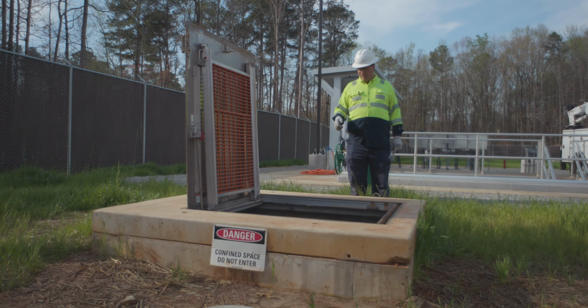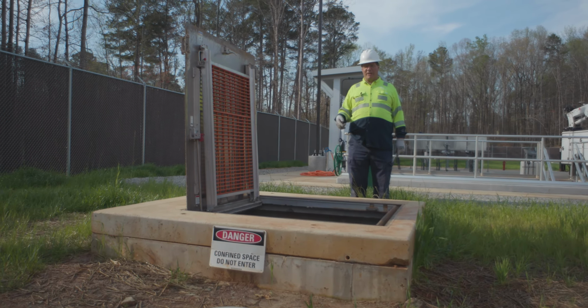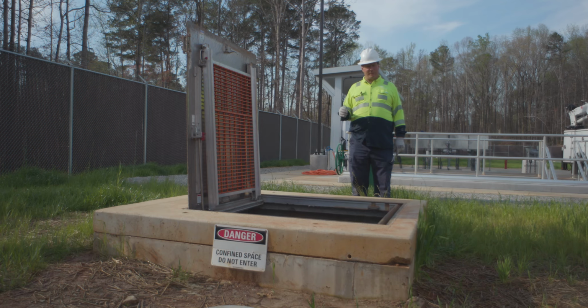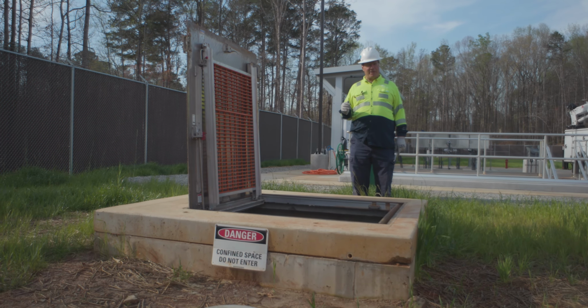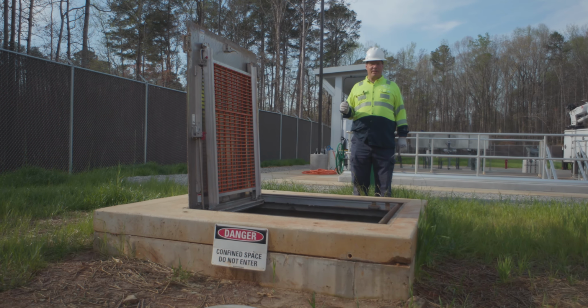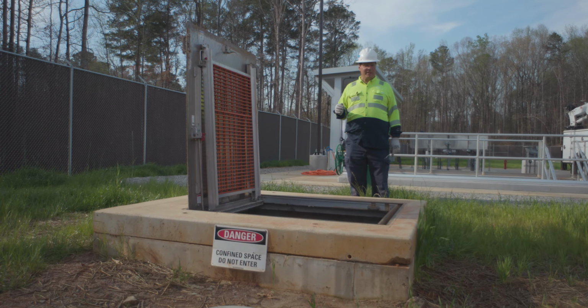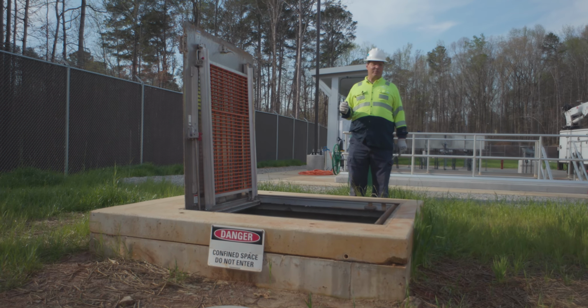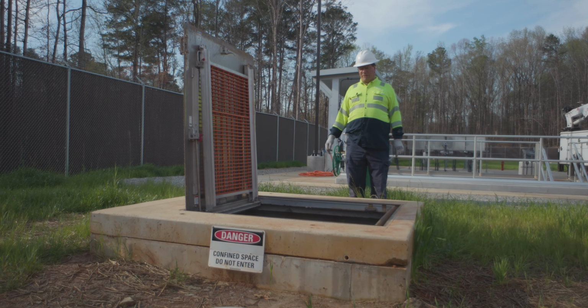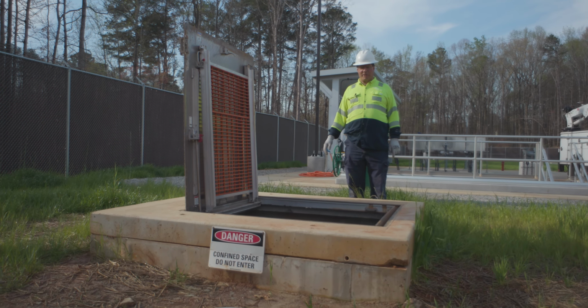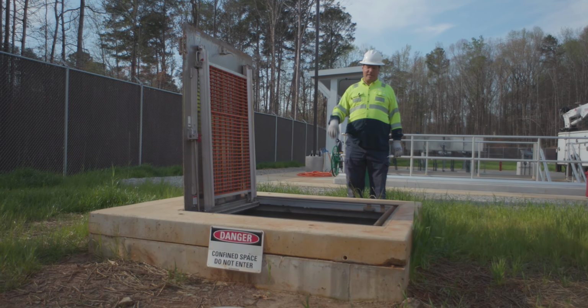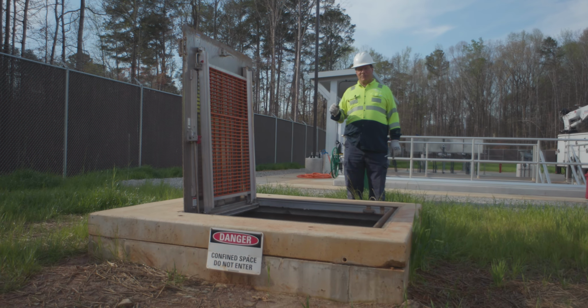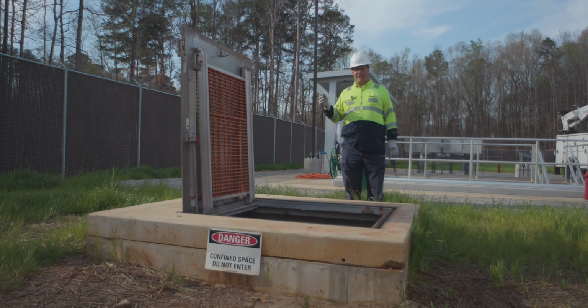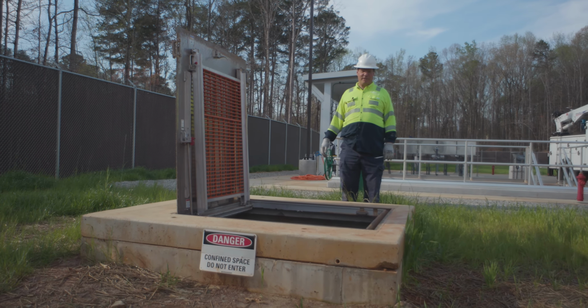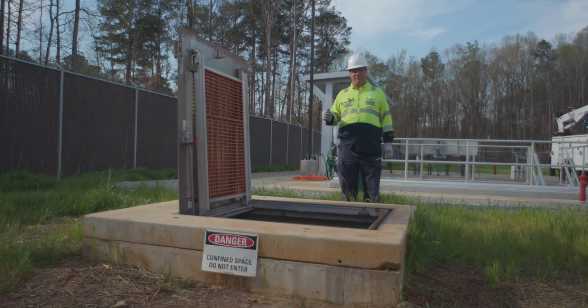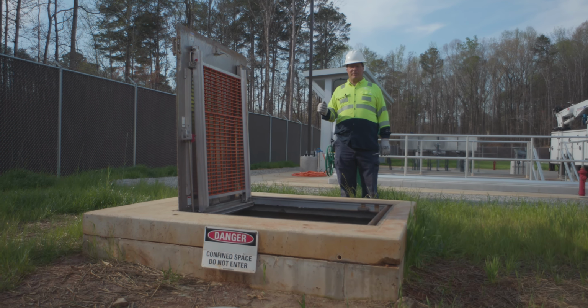But it could also help you with a faulty air release valve. If the static pressure starts getting higher and higher, that could indicate that an air release valve has stopped working and is increasing the resting pressure when the pump is running, or it could just be a closed valve. A lot of times when the pump is running and the pressure keeps getting higher and higher, that usually indicates a pressure valve or an air release valve failure as well.